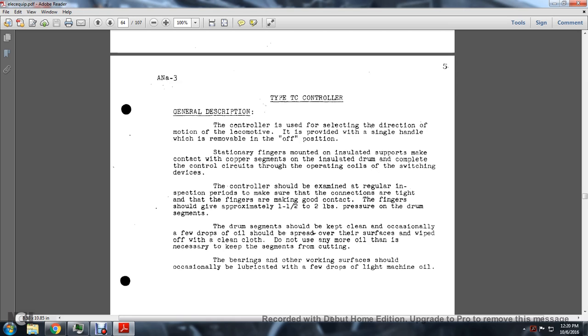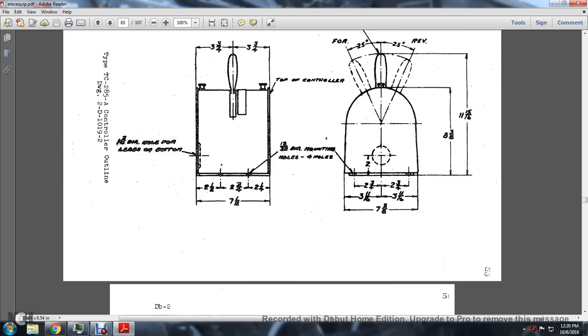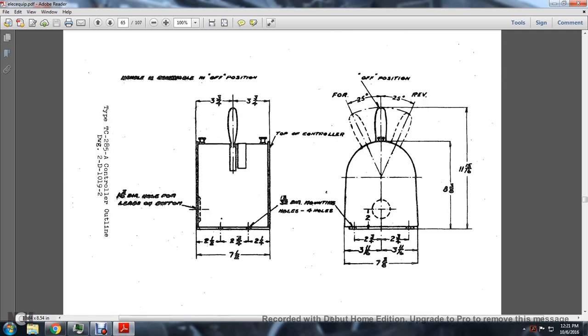The control should be examined at regular inspection periods. Make sure that the connections are tight and that the fingers are making good contact. Fingers should give approximately one and a half to two pounds pressure on the drum segment. The drum segments should be clean and occasionally a few drops of oil should be spread over the surface and wiped off with a clean cloth. Do not use any more oil than is necessary. Bearings and other working surfaces should occasionally be lubricated with a few drops of light machine oil.